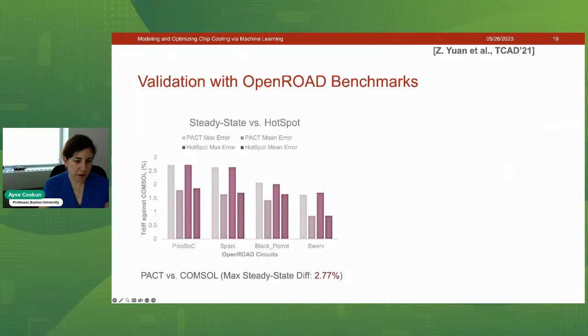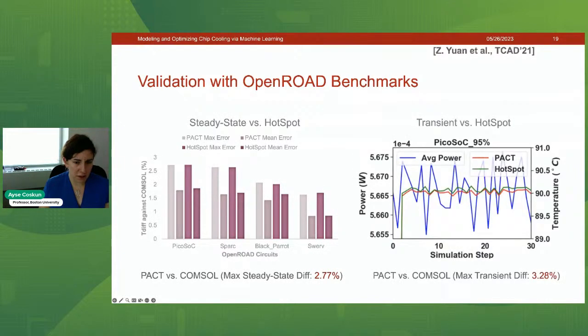So when we did validation with OpenRoad benchmarks, we saw highly promising results. So like I mentioned before, the comparisons to finite element methods that are modeled for the equivalent chips and cooling mechanisms, we see a difference of less than 3% error. And this is similar to what any other compact thermal model typically would experience, such as HotSpot. So we got good error rate, and our results, as you see on the right side here, matches that of HotSpot in terms of the runtime transient response as well. And our difference from, again, COMSOL in terms of the transient is also around 3%.